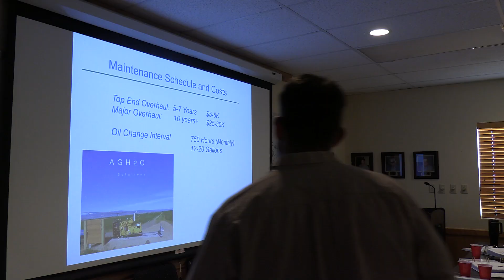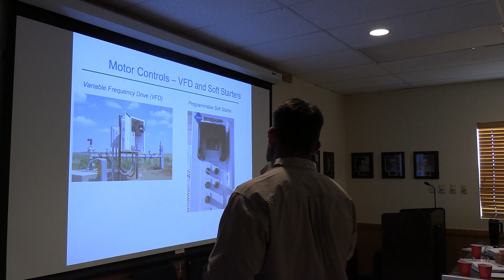The variable frequency drive and the soft starter become a very important non-optional tool for you on your submersibles. We often can get away with a pumping plant panel on submersibles just on because they're usually low load and the line can handle that. When it's a gen set, you don't want your gen set to handle that because it's not a big enough, robust enough generator. It's going to drag a little bit. It can't recover so quickly.